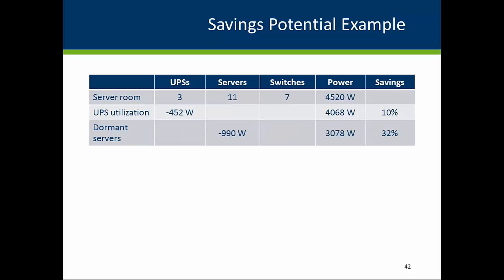Next, let's look at the servers. Since the NRDC study estimates that up to 30% of the servers in an SEDC are dormant, let's assume that we can power down 3 of the 11 servers, each with an average power draw of 330 watts. That brings an additional savings of 990 watts and a total savings of about 32%, and a reduction in server power draw of about 1.5 kW.